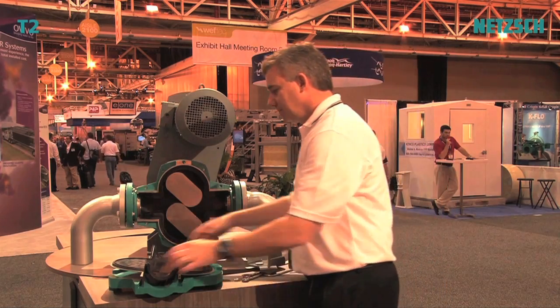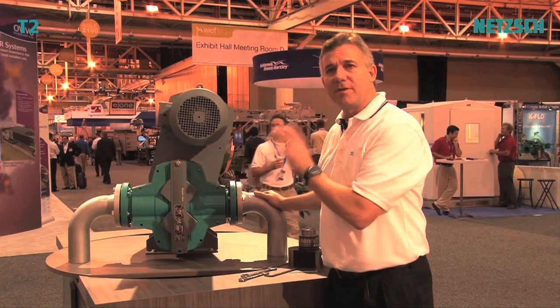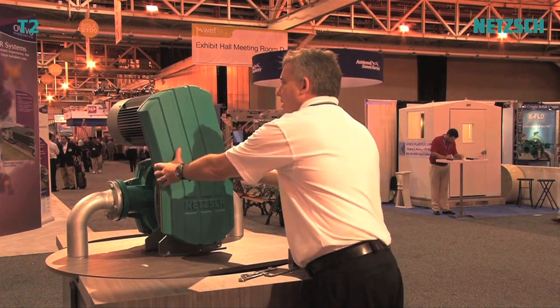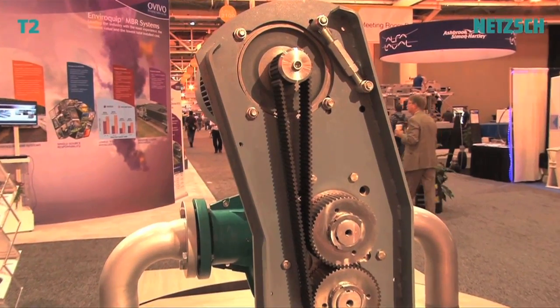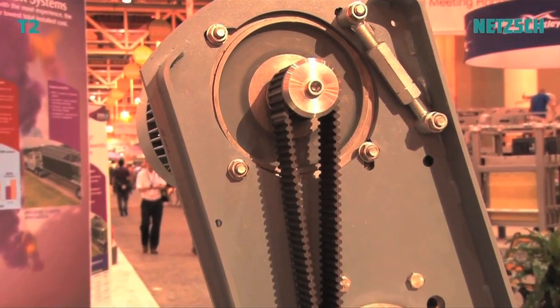Put on the front cover. This is full service in place — not only from the front end but also the back end. Instead of timing gears, NETZSCH developed a pump that uses a timing belt. So there's no messy oil to service, no gearbox to maintain, and the footprint is smaller.